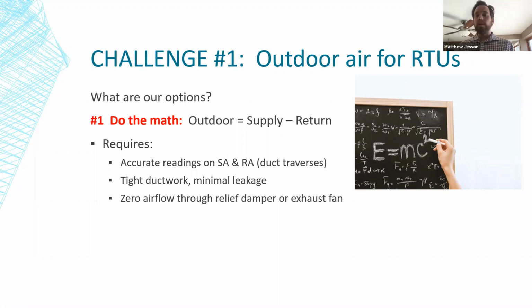You need good tight ductwork, minimal leakage, which is always a good thing. But if you have too much leakage between your traverse and the unit, that can throw this off a lot. And you need to have no airflow going through anything else. Nothing through the relief damper or exhaust fan. You think about it, you just draw your box, and your box has return air coming in, supply air going out, outdoor air coming in. If there's anything else, then suddenly that arithmetic doesn't work.